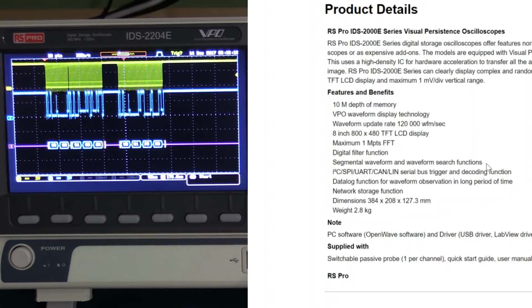When you have waveforms that are changing, maybe they're rapid bursts and then not much activity and then rapid bursts, you often, when you're using the trigger, can capture one of those bursts, but the subsequent events may be beyond the range of the captured data because there is not the time to capture it all before you run out of memory, or the capture speed is not fast enough to get the resolution. Your effective sampling rate reduces when you start trying to slow down the overall timescale. So say maybe it's 2 or 3 seconds worth of events that are happening on something, and they're just little bursts within that, because when you have linear memory, you capture the data for that entire 2 or 3 seconds. That will rapidly fill up your memory.